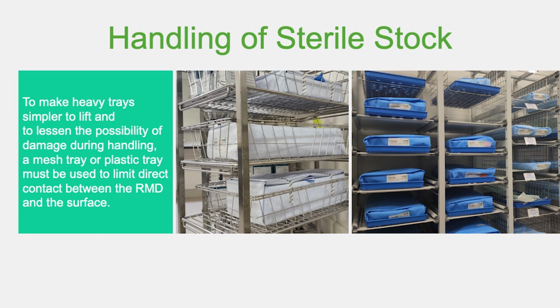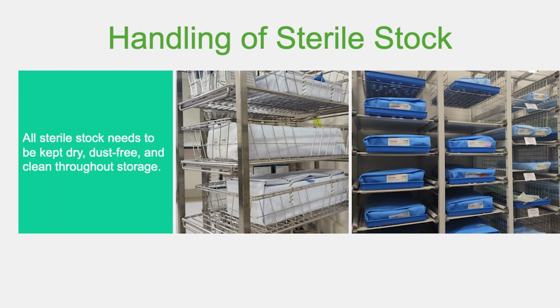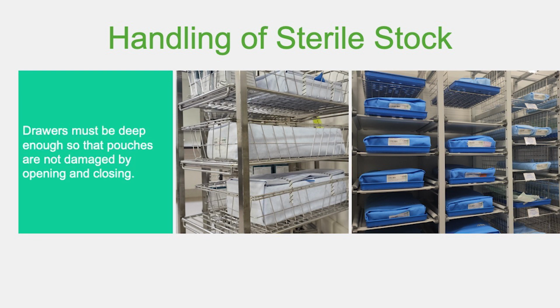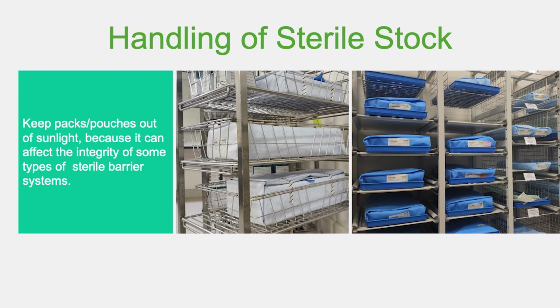To make heavy trays simpler to lift and to lessen the possibility of damage during handling, a mesh tray or plastic tray must be used to limit direct contact between the RMD and the surface. All sterile stock needs to be kept dry, dust-free, and clean throughout the storage. Drawers must be deep enough so that pouches are not damaged by opening and closing. Keep bags and pouches out of sunlight because it can affect the integrity of some types of sterile barrier systems.